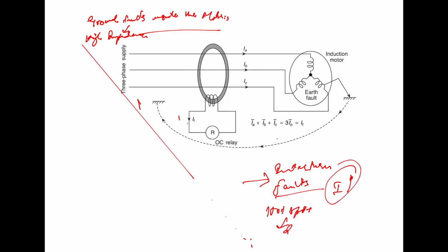So no specific protection against the interturn fault is needed for most motors. However, in big motors it can be required. So embedded temperature detectors may be relied upon to provide the protection against that. For the big motors, embedded temperature detectors can be used.